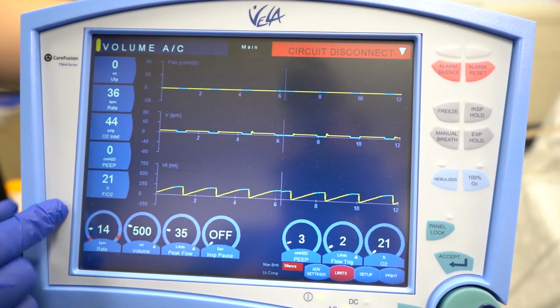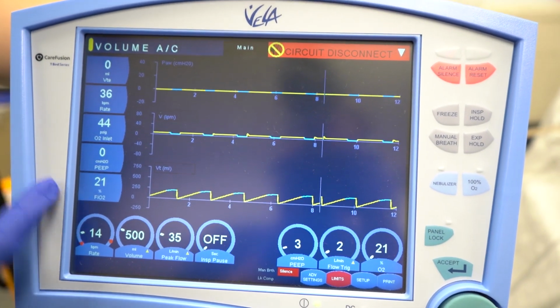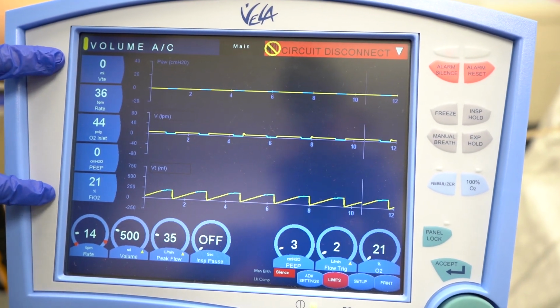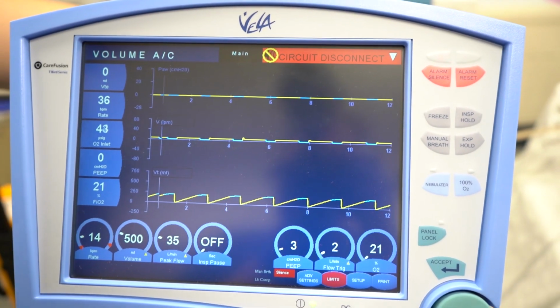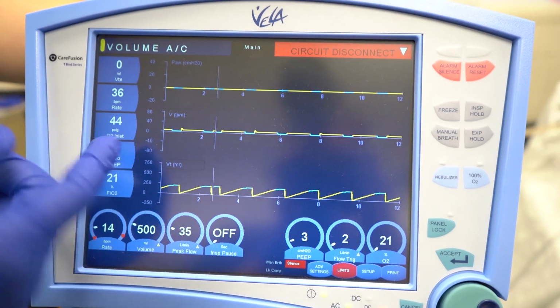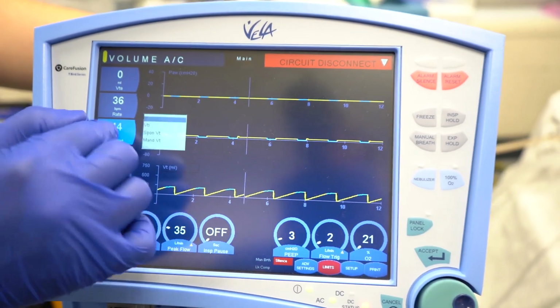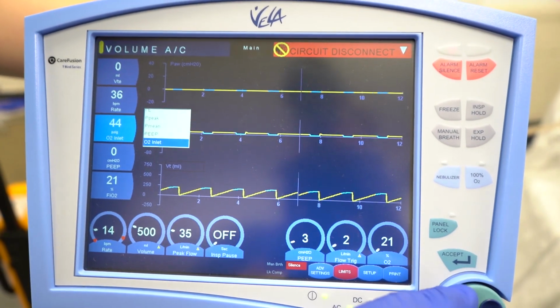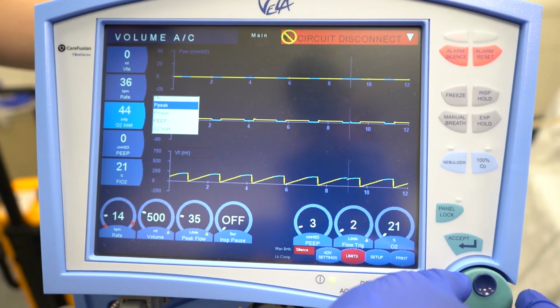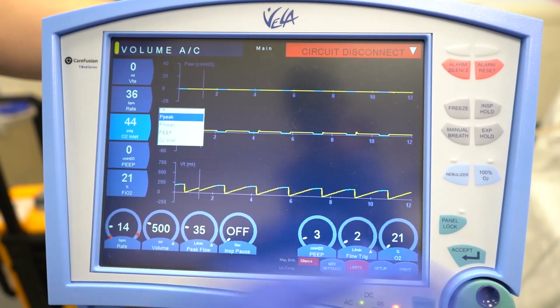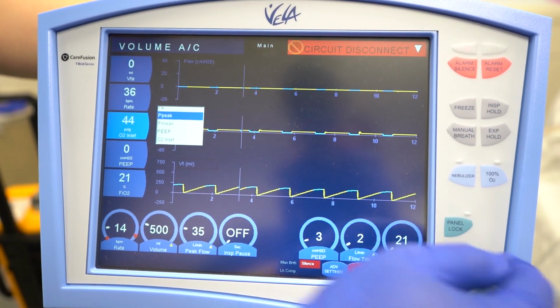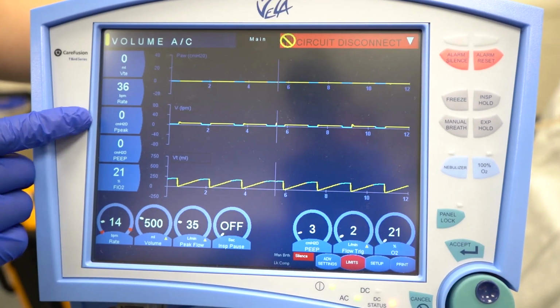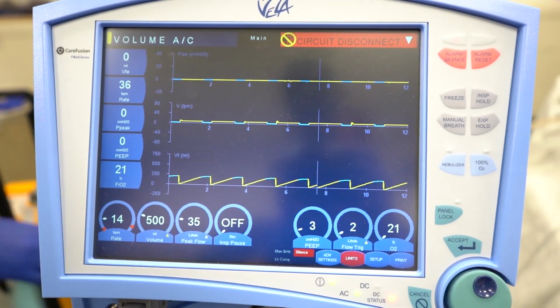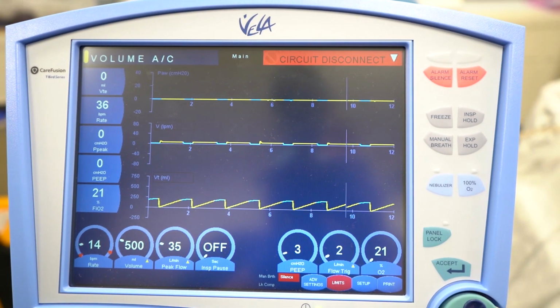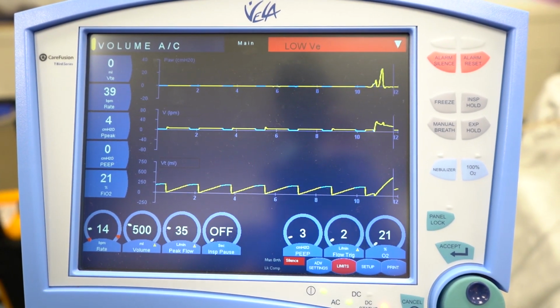Your parameters are located on the left hand side. You can only view five at a time, but you can adjust which ones are being shown. So for instance, this one, you don't really need to know the PSI of the oxygen, so you can change that to whatever parameter you want to see. So let's choose peak pressure. If you want peak pressure, you just scroll up to select peak pressure and then hit accept. So now your peak pressure will be displayed.